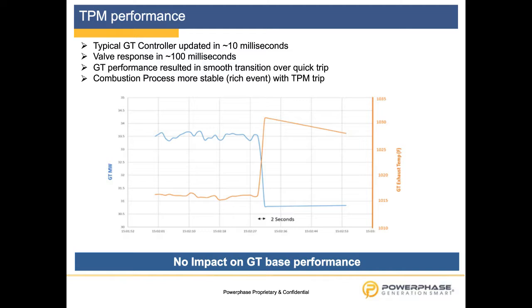The airflow was reduced immediately, so the gas turbine went back to baseload. In this very instant, the exhaust gas temperature increased because of the missing mass flow. The fuel air ratio went into a richer position, and with the missing mass flow, the exhaust gas temperature automatically goes back to where it was over a shorter time frame. That is all done automatically by the GT controller, and our injected air is not going to interfere in that particular operation mode.